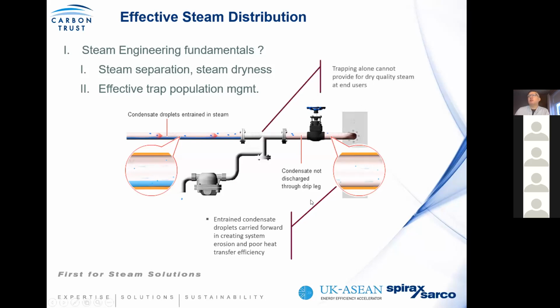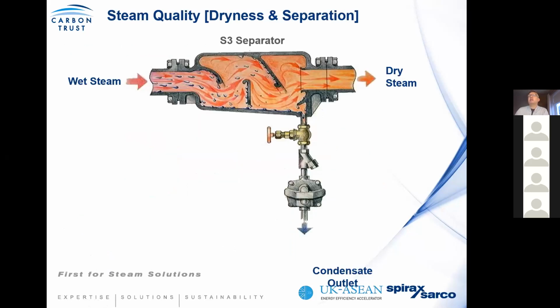It is therefore important to recognize that trapping alone, even with a best-in-class trap installation, will not remove all the water. It'll remove the water in the sump of the pipe, but not that entrained in the steam itself. Therefore, we should look at separation, because the function of a separator is to basically remove these water droplets. As wet steam moves through your distribution system, the separator reduces the velocity of steam as it transitions through. In doing so, the water droplets under their own gravity will fall out of suspension, collect at the base of the separator, and get removed effectively through proper trapping.